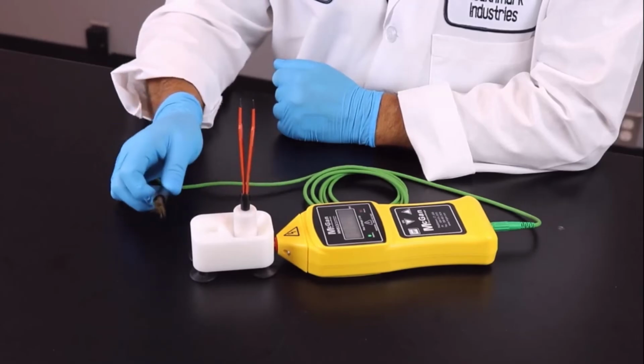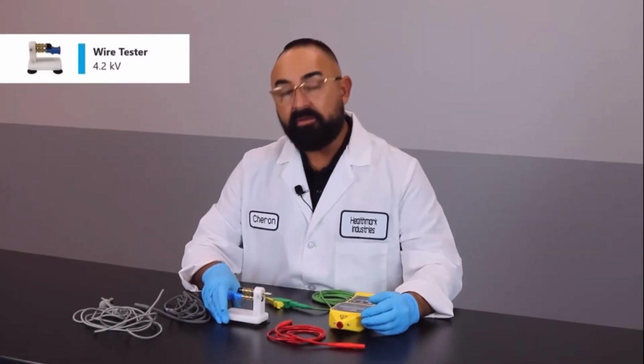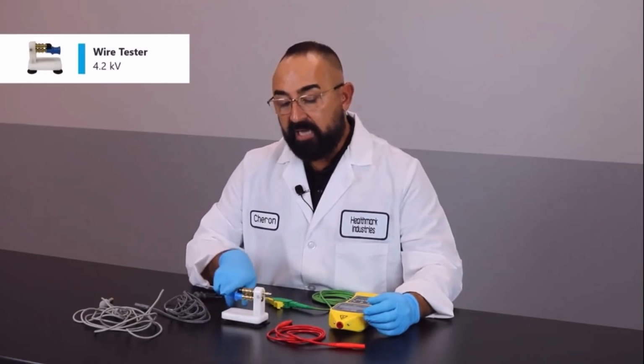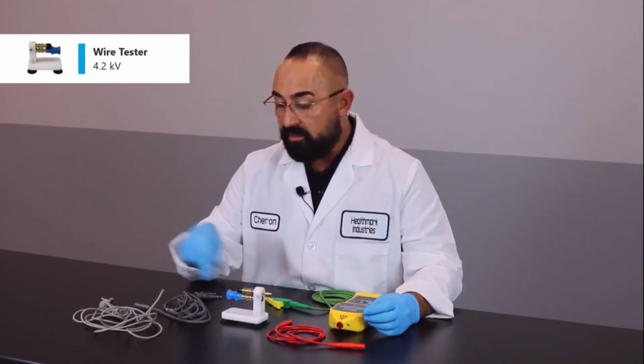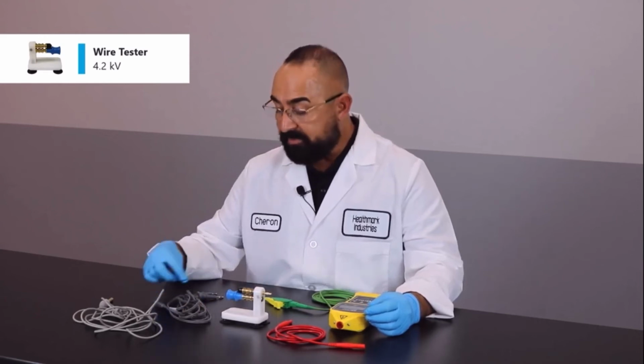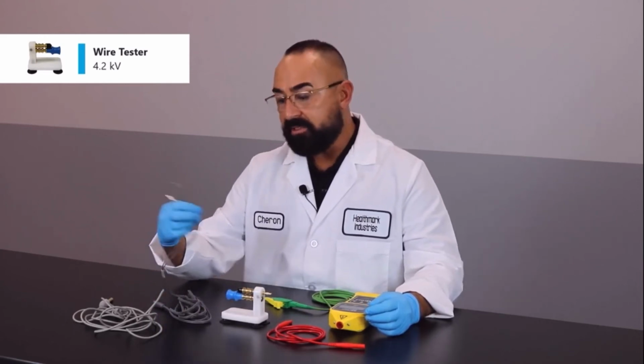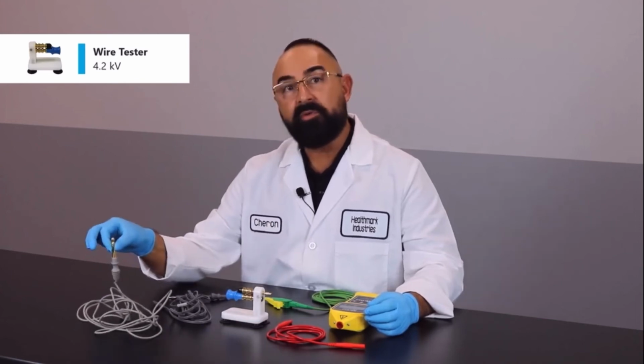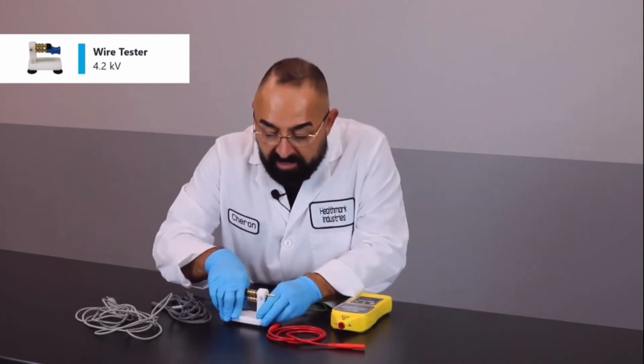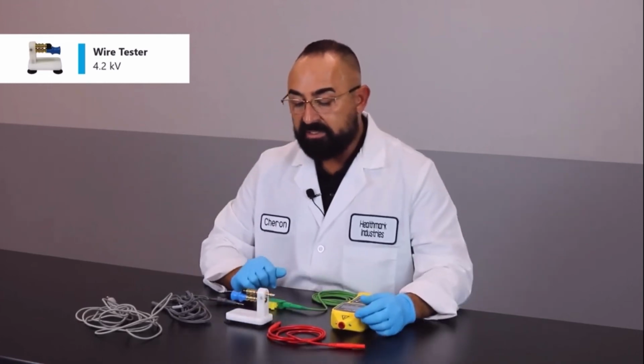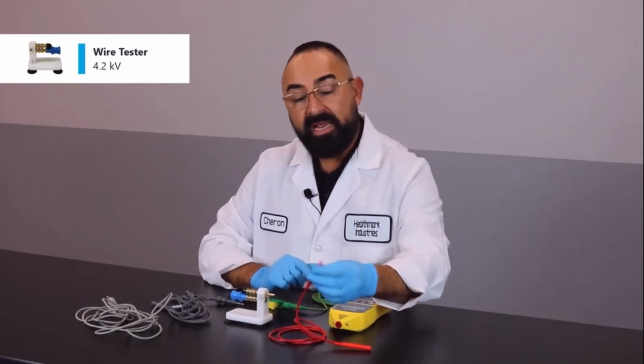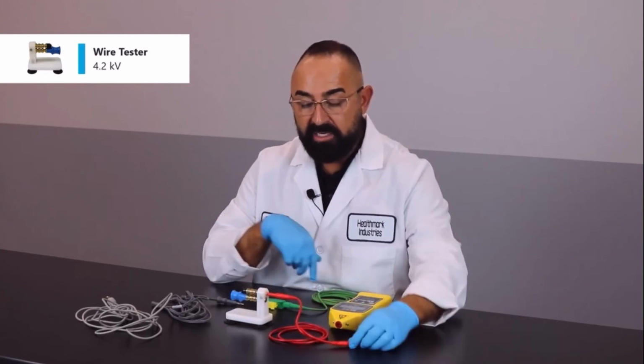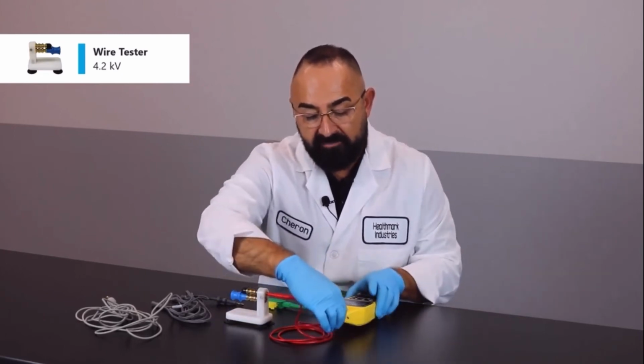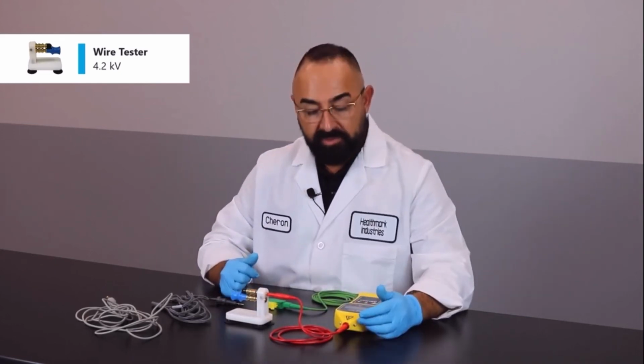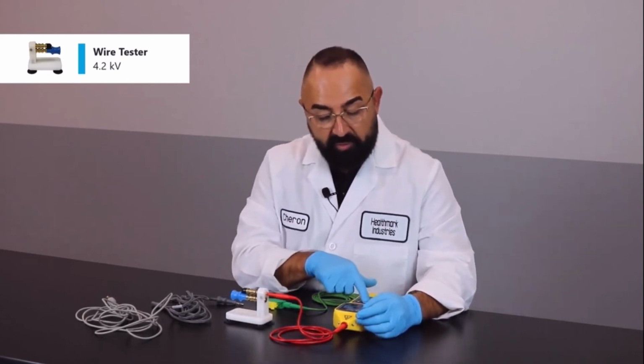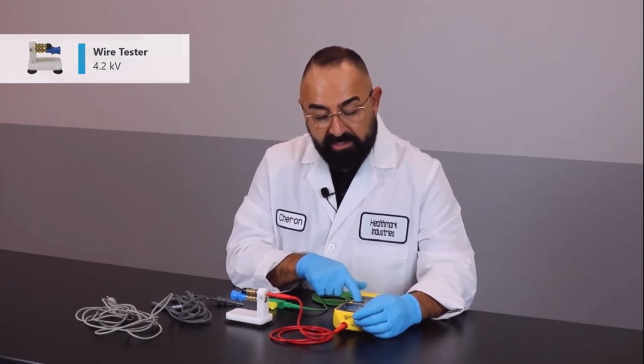all the way down. So this accessory here is called a wire testing fixture. This is actually to test the integrity, which would be the outside of your cables and cords. Specifically, your bipolar cords that are reusable and your monopolar reusable cords as well. So you get your suction cups and you're going to put that onto your workstation. You're going to take your red HV wire and you're going to plug one end into your wire fixture and the other end to your unit. This specific setting voltage is 4.2, so we'll set our unit to 4.2.